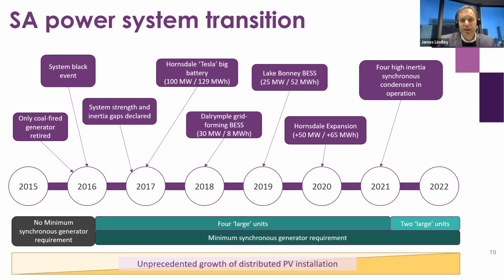Electranet, the transmission company in South Australia, then had a process to try and close those gaps, and the most efficient way of closing that gap was found to be construction and commissioning of 4 large high inertia synchronous condensers. That process kicked off in 2017.